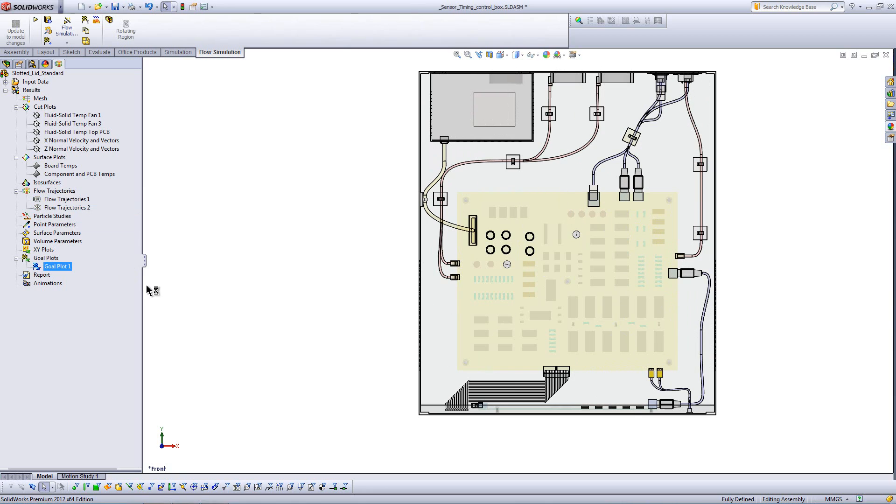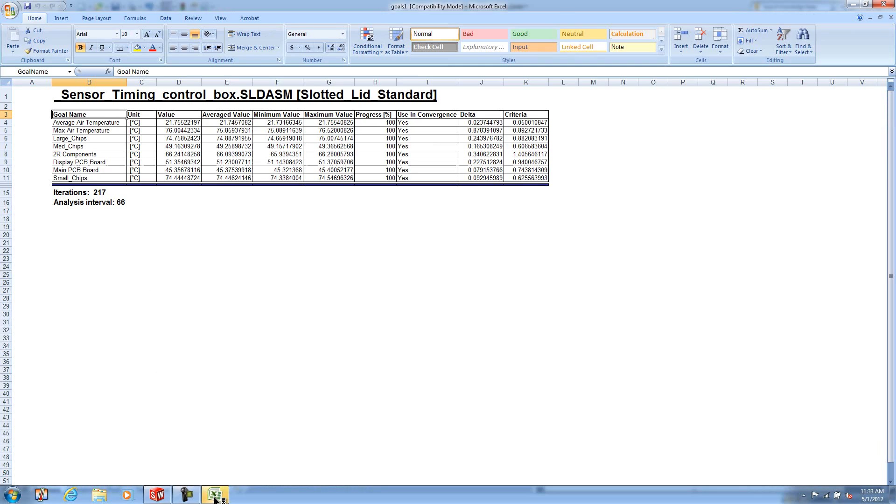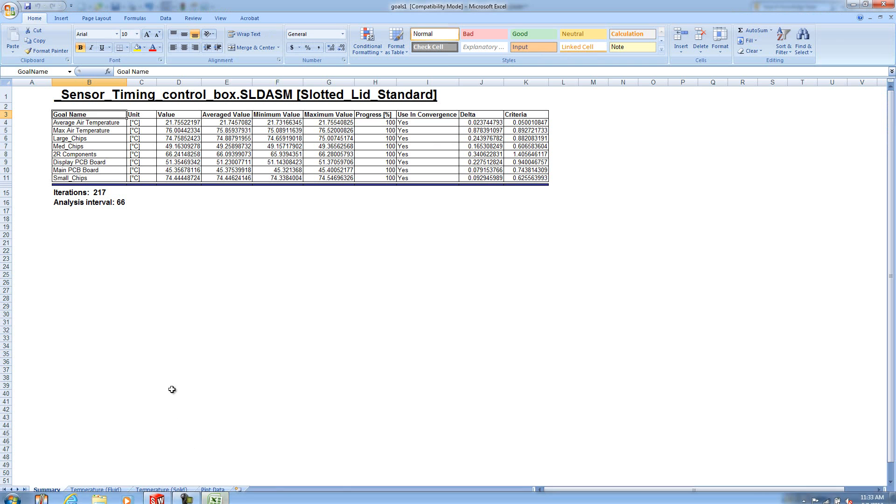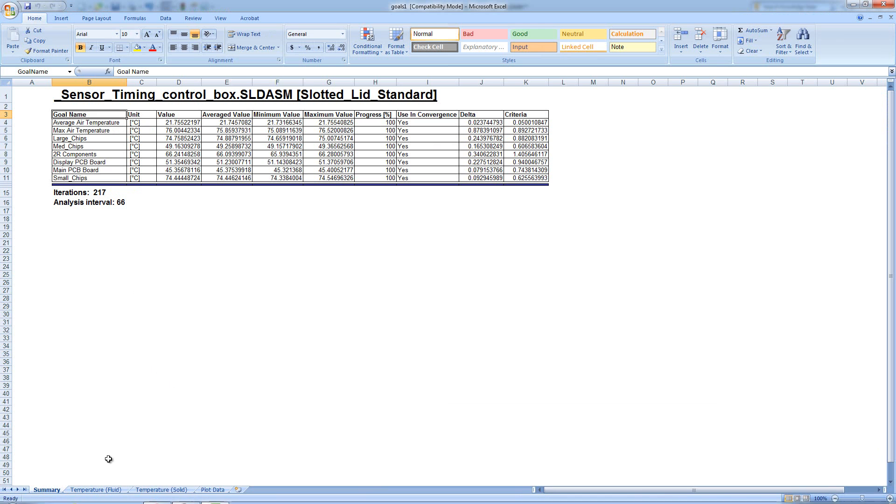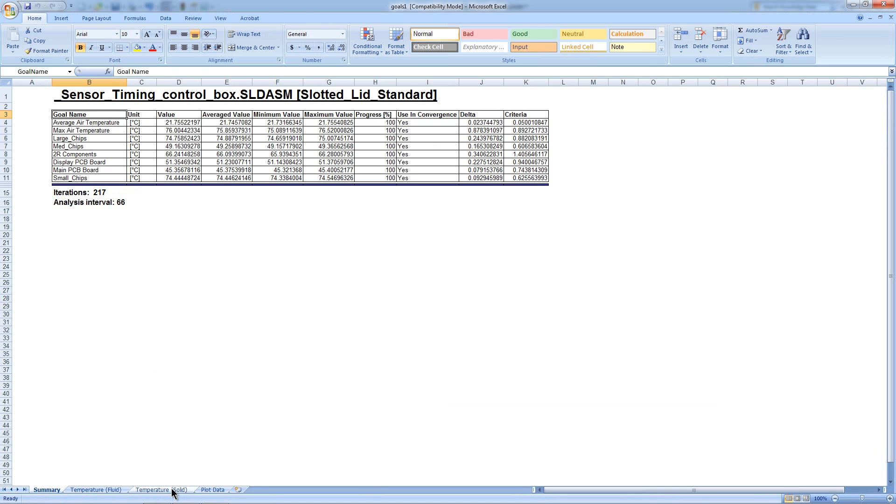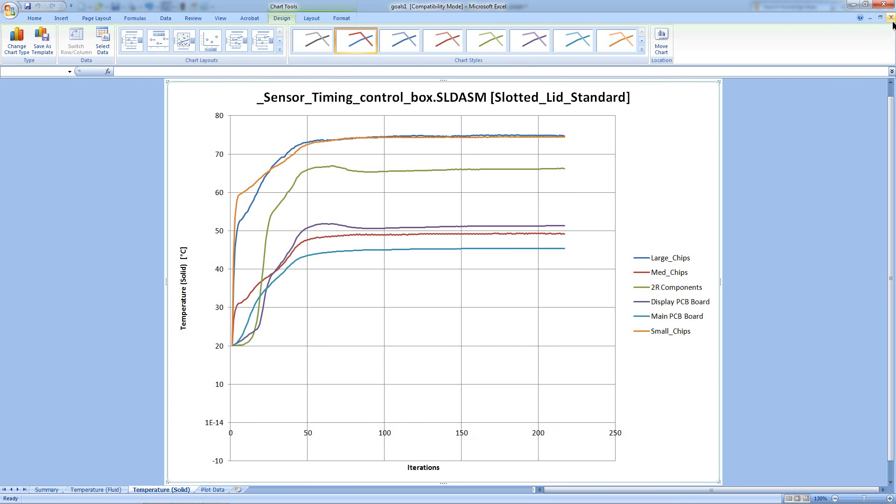So let's see if we can make this design a little bit more effective. Remember those goals we set up? I can right-click and export those to Excel, and this is going to give me the more quantitative information. And remember my design goal, keep things maybe below 65 degrees C. So we can do that right away and then go ahead and evaluate these goals with those three different design options of the three different enclosures. And what do we see? The yellow is actually the winner with no vents.